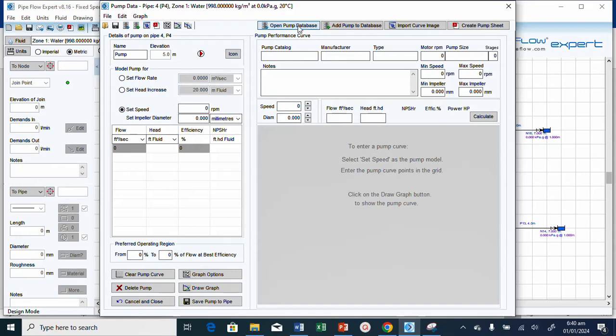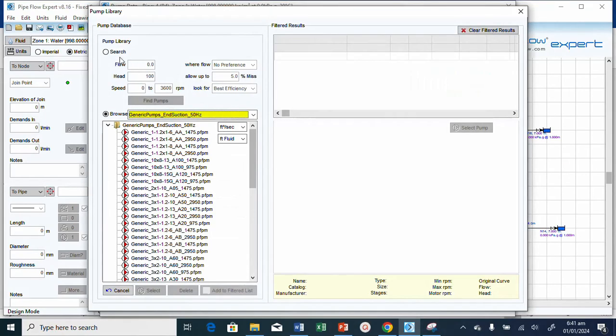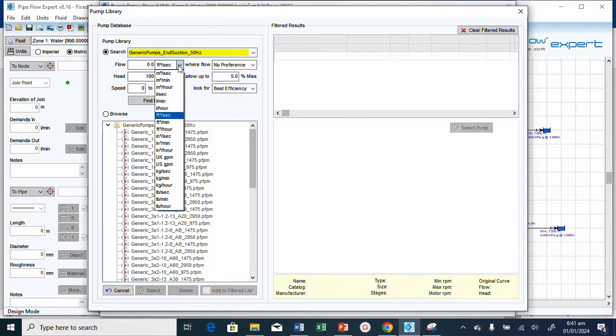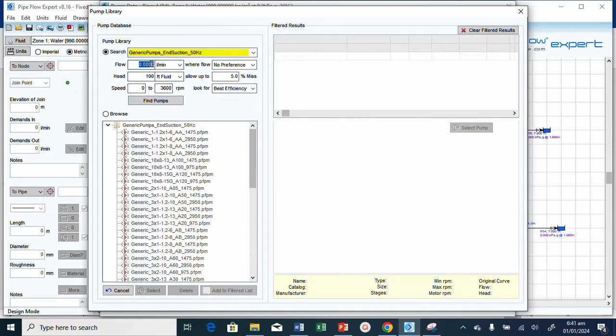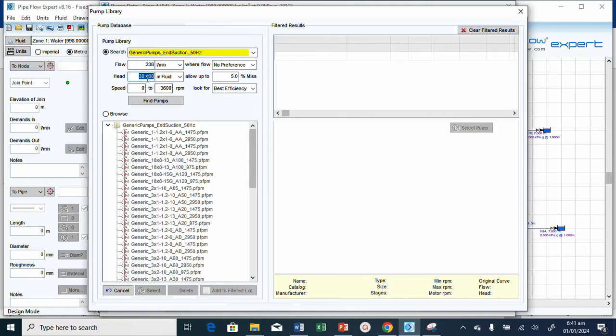Go to the pump database, open it, go to search. We need to search for the pump that can deliver. We're going to make selections from what we've already gotten. We need to change this to liter per minute. The value here is the flow rates, the total flow rates. The controlled flow is 230. The head is in meter fluid. This should be 20.